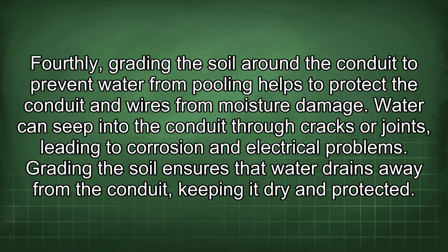Fourthly, grading the soil around the conduit to prevent water from pooling helps to protect the conduits and wires from moisture damage. Water can seep into the conduit through cracks or joints, leading to corrosion and electrical problems. Grading the soil ensures that water drains away from the conduit, keeping it dry and protected.